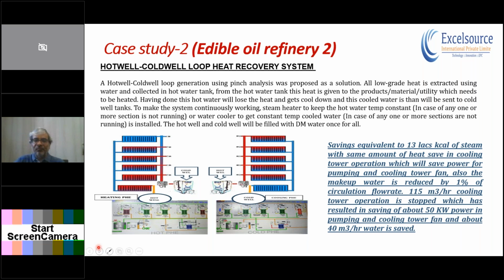But here, this is actually a plant with cogeneration. So when we have done this, we have saved the amount of steam which was utilized for heating the product. So the steam available in this particular cogen is now available for generation of more power. So we have taken that additional equivalent amount of steam to the condensing mode of the turbine, and the plant is operating with the same amount of coal, less water requirement, and producing more power also.